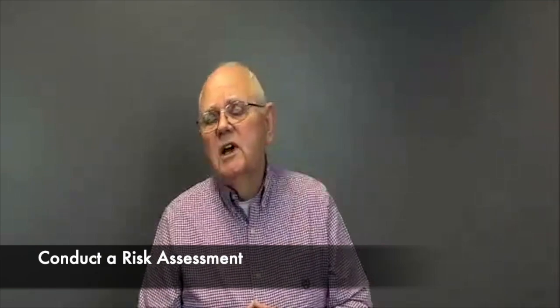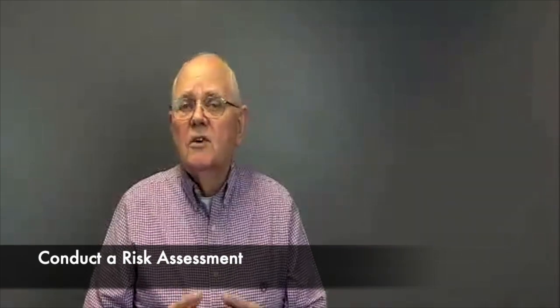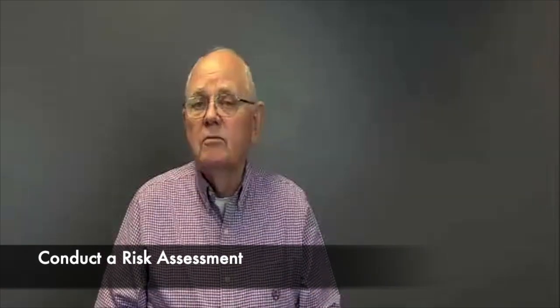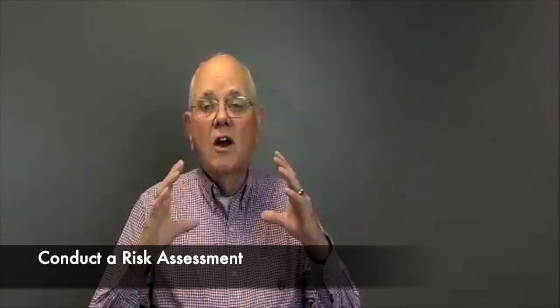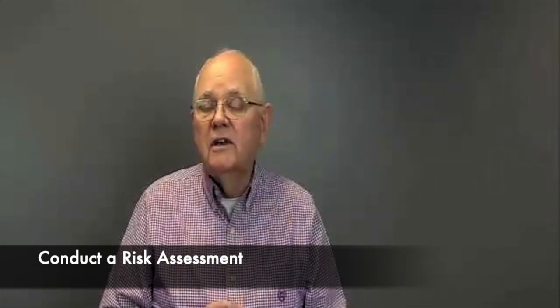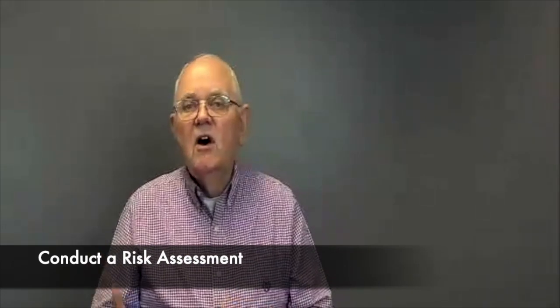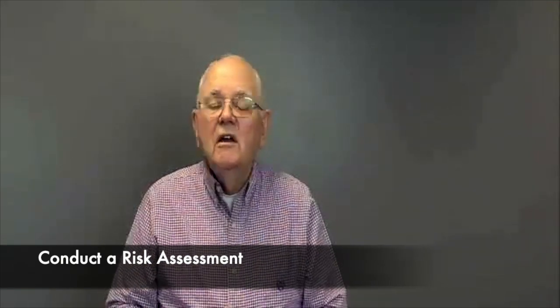Now, let's talk a little bit about the risk assessment when it comes to medium voltage. First of all, some of our numbers are going to change. If you have the arc flash warning labels on your equipment, certainly you're going to use those. The arc flash warning labels will either have the incident energy levels at a certain working distance, or it will have the PPE category method for you. And of course, it'll also have the voltage information there.